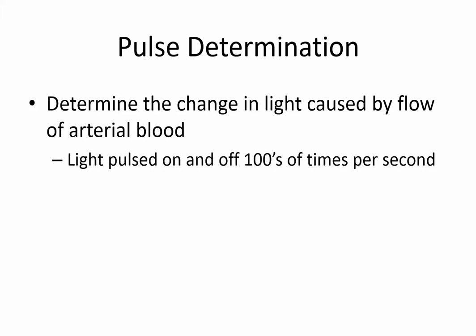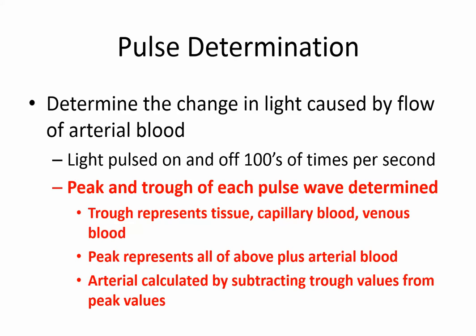Pulse is an integral part of pulse oximetry. The pulse is determined by the change in light caused by flow of arterial blood. So light is pulsed on and off hundreds of times per second, and a peak and trough of each arterial pulse wave is determined. The trough represents the tissue, capillary blood, and venous blood, and the peak represents all of that plus that blood which was added as a result of the arterial pulse.